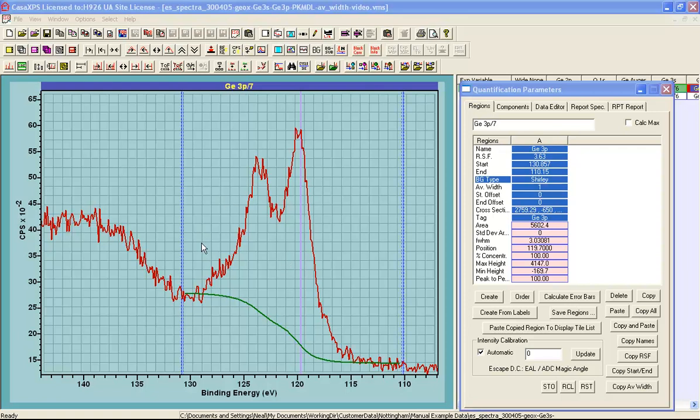An alternative to using improved sensitivity is to increase the dwell time per bin. And this, because of Poisson statistics for pulse counted data, will improve the precision with which we know the intensity for each data bin. Now the consequences of increasing the dwell time is that you increase the measurement time and potentially the degradation of the sample. So this is not always the best option. However for a given measurement, the influence of dwell time can be used to improve the precision with which we identify the intensity for these end points of the background. And this is performed using the average width.